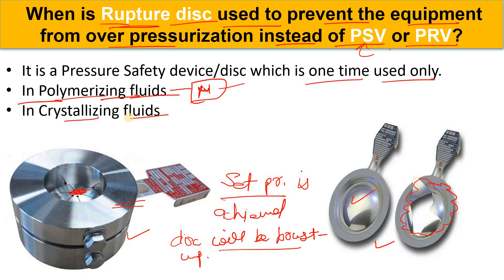We also use the rupture disk in clean fluid applications. For example, in a heat exchanger — suppose on the tube side there is a process fluid and on the shell side there is condensate — you could use a rupture disk there because it will not cause any harmful impact to the environment or personnel. When it ruptures, the environment will not be polluted since it is only condensate.